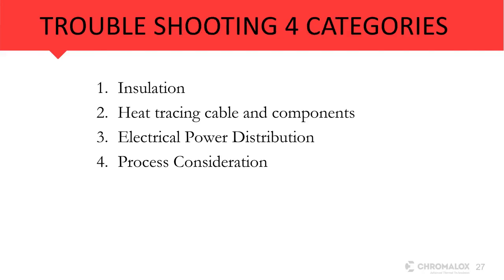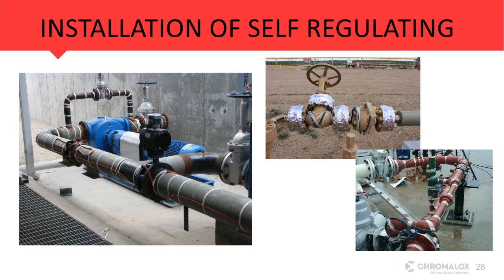And those all fall into insulation, heat tracing, cable and components, our electrical power distribution system, and then process, any kind of process considerations that we need to be aware of. If we look at a typical heat tracing system that's uninsulated, if you take a look at some of these pictures, you can see that around valves, around pipe shoes, flanges, we have extra cable, and that's to account for those heat losses that we have in those specific areas.